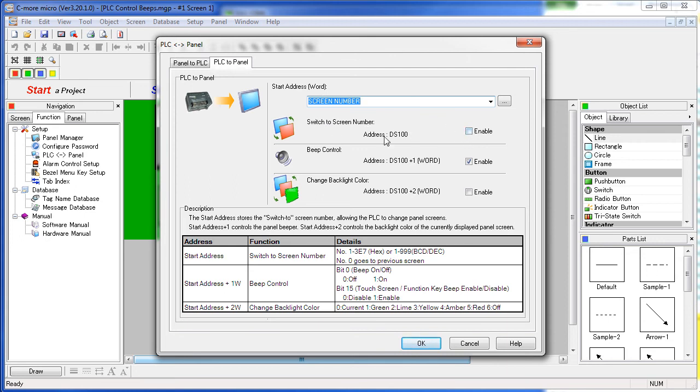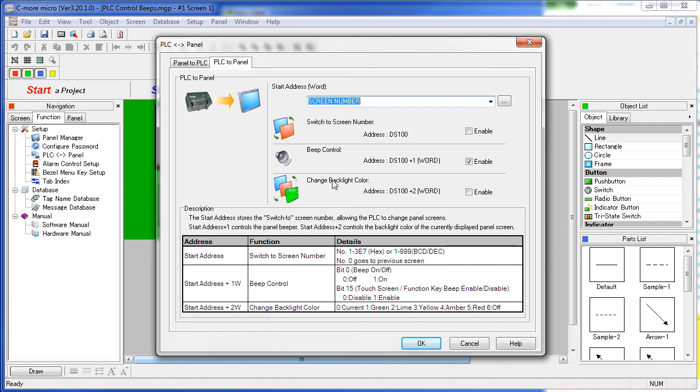Then the very next tag at that address plus 1, if we enable it, is our beep control word. And by the way, there is a third one at the screen number tag plus 2 that allows the PLC to control the backlight color of the screen. But this video is about beep control so we are just going to enable that one right now. And that's all there is to it.